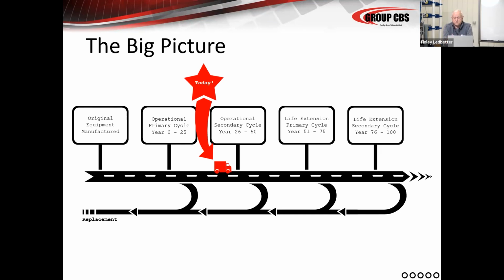Then you see these life extension segments, primary and secondary life cycles. That's really where you start to double and triple the proposed life of the equipment. And we have all kinds of things available to us to do that today. Converting insulation, converting controls, doing all sorts of things to bring the equipment up to where it will live longer. And we're going to talk about that a little bit today, and we're going to zoom in and talk about it in great detail in the next 3 segments. So this is the life cycle, essentially the big picture. You've got when the equipment is manufactured, its primary cycle, its secondary cycle, its primary life extension cycle, and its secondary life extension cycle.